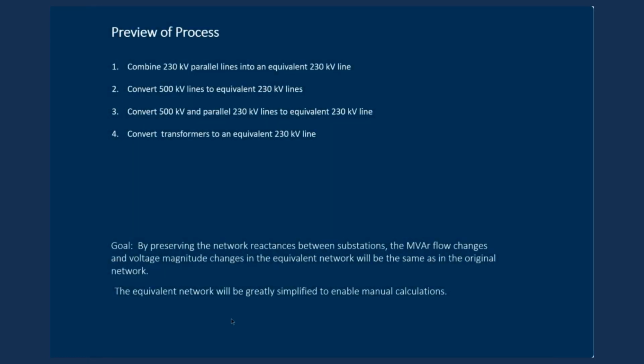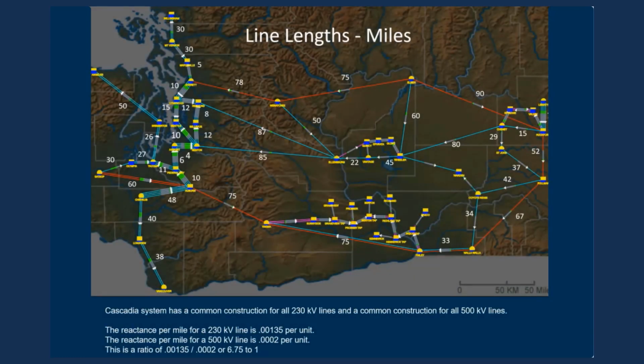Our goal is to preserve the network reactances between substations so that the megavar flow changes and the voltage magnitude changes in the equivalent network will be the same as in the original network. However, the equivalent network will be greatly simplified to enable manual calculations. So here is a geographic map of the Cascadia system with the lengths of the 500 kV lines and the 230 kV lines shown in miles. The magenta are the 115, and for our analysis they will not have a significant impact on our calculations.